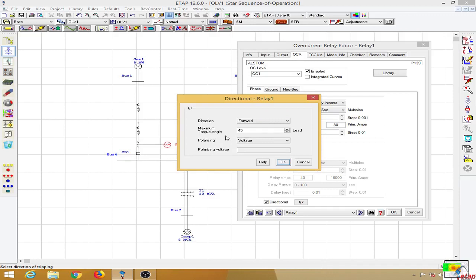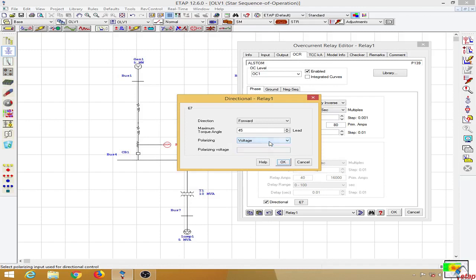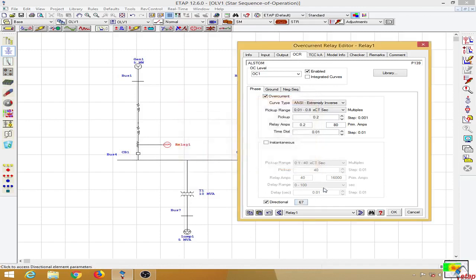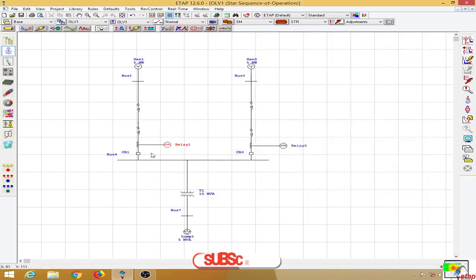The maximum torque angle (MTA) is set to 45 degrees lead. The MTA that we can provide to a relay is in the range of 30 to 60 degrees. Most relays offer the option of selecting 30, 45, or 60 degrees, and this depends upon the line impedance. We can also choose the polarizing voltage.